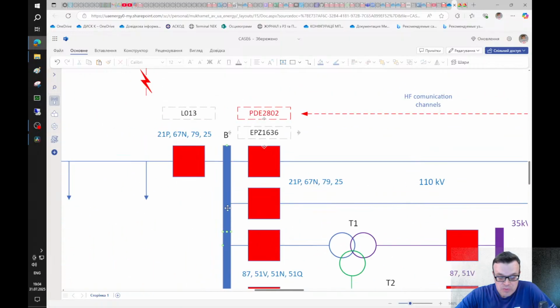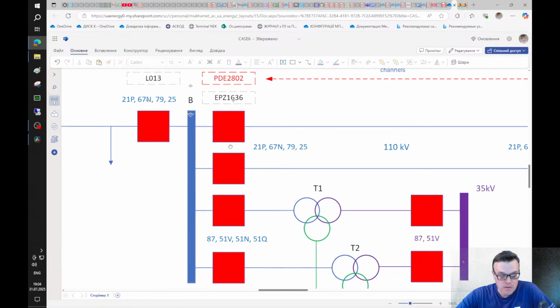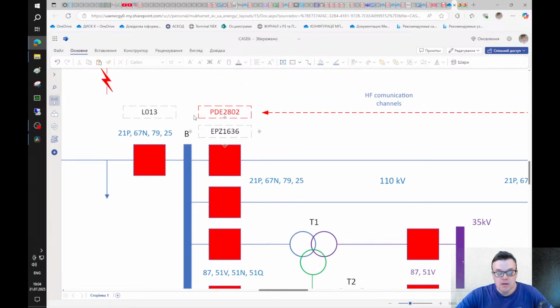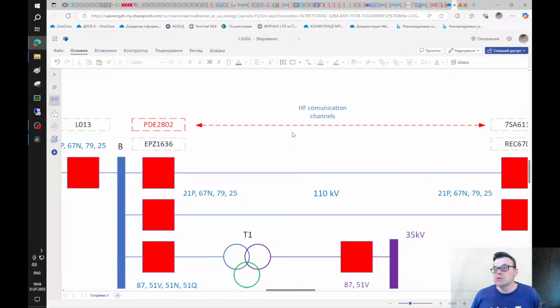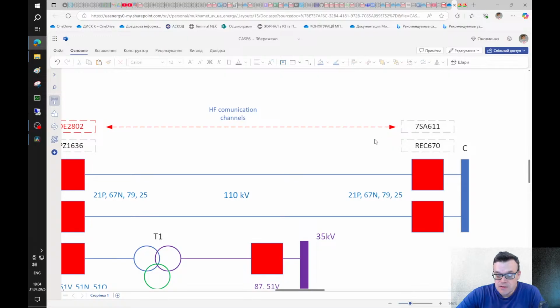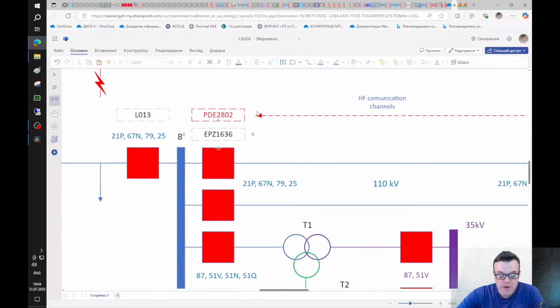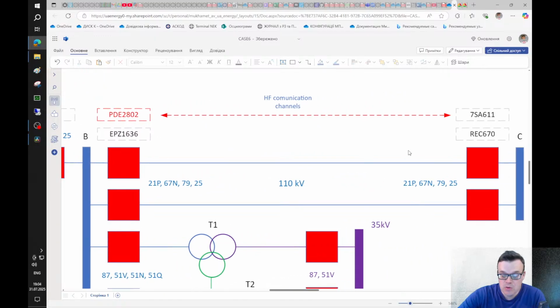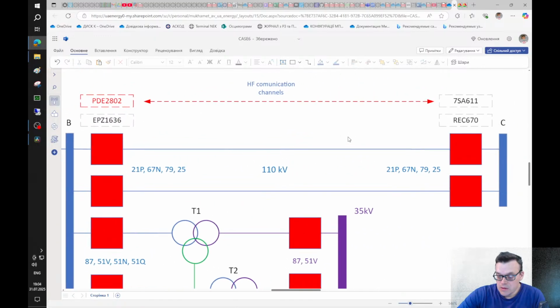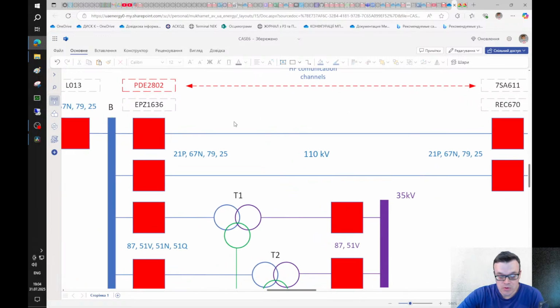From the substation power plant B side, all the protections are almost all old electromechanical protections from the Soviet era, and this protection uses a POTT scheme with the 7SA, but at the time of the event it was out of service, so only backup protection functions worked on each side.